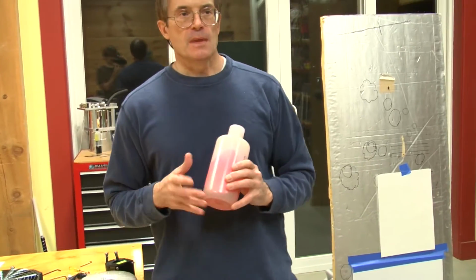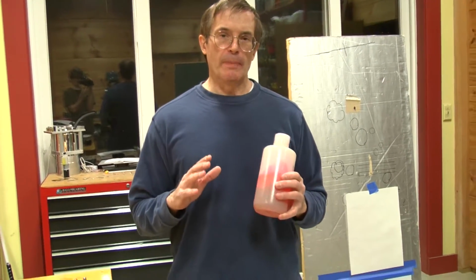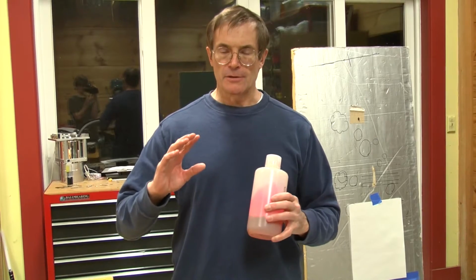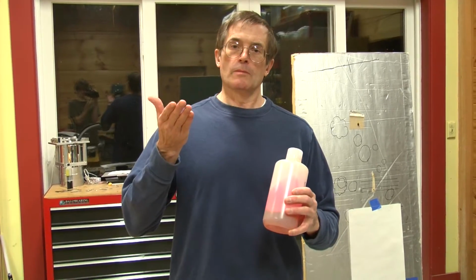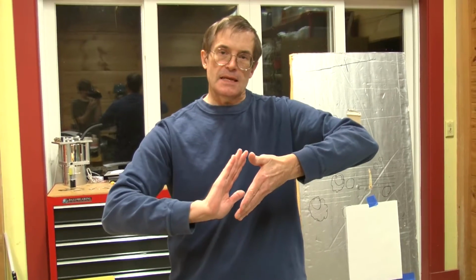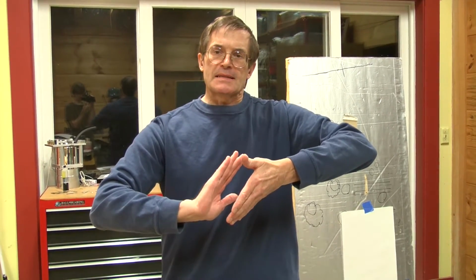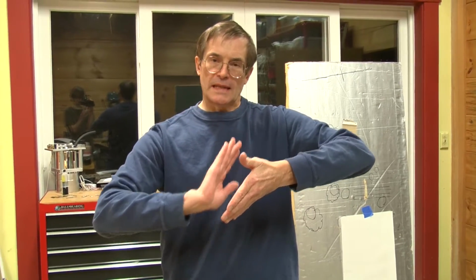And that is that the organic molecules that make up these dyes have loosely bound electrons. They're called the pi electrons. And these electrons, which are in pairs, are stimulated by the photons, the energy from the flash lamp. And when they're excited, they absorb some of that visible light and then spontaneously will decay and produce either incoherent or, if stimulated, coherent laser light. Because those electrons are in the same energy level, they're in opposite spin states, the Pauli exclusion principle. And so when stimulated and they remain in an opposite spin state, they can decay very quickly. That's the spontaneous state that produces the laser output. That state exists only for a couple of nanoseconds before it will decay spontaneously.